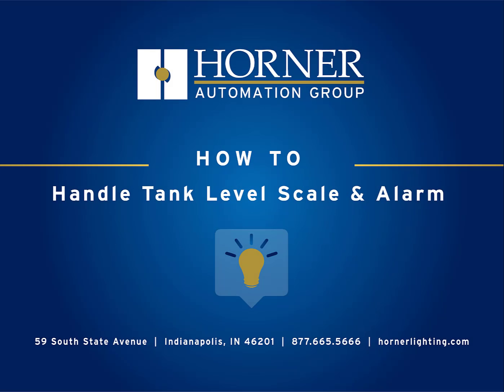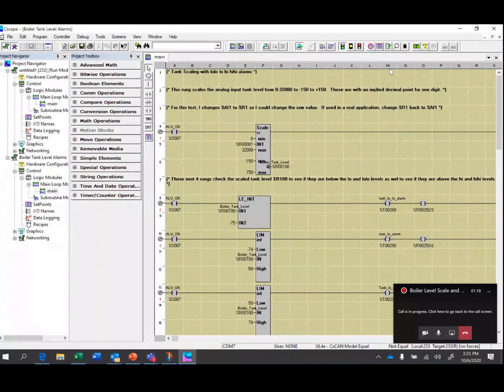We're going to do a little video here on an application to do analog scaling for a tank level, as well as to set high-high, high, low, and low-low alarms on that analog value. So the first thing we're going to do, I've got the application written here, but we'll go back to the logic here in a little bit. We're going to start out in the graphics end of things.